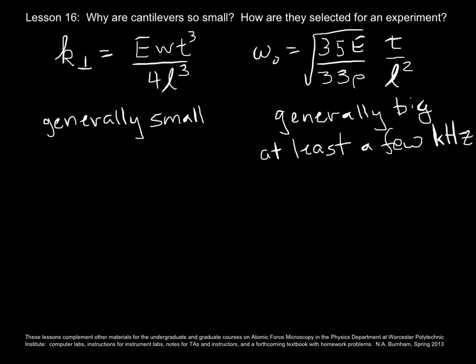Here are the two important equations in this lesson, that of the spring constant in the normal direction and the resonant frequency of that spring constant. In selecting a cantilever for the spring constant, you would be thinking about range and resolution. So if you want to apply a large range of forces, then you need a bigger spring constant. If you want good force resolution, you would want a smaller spring constant.